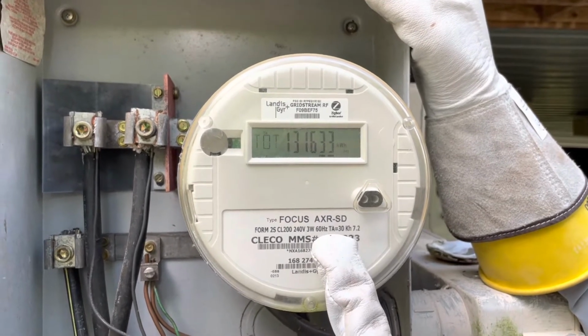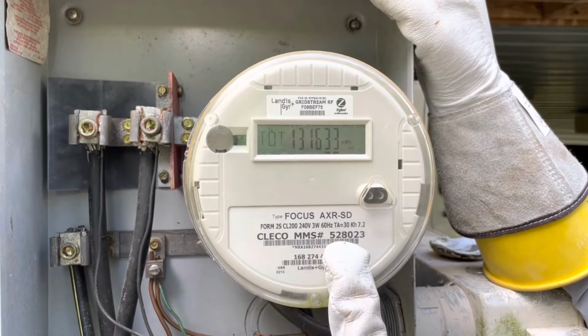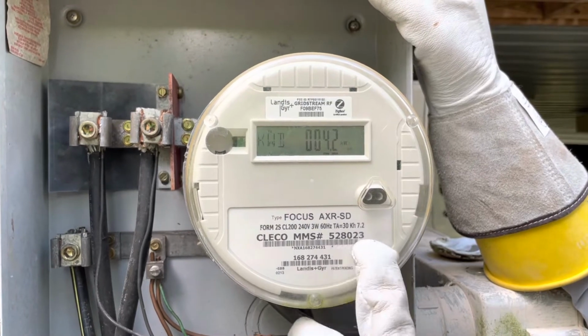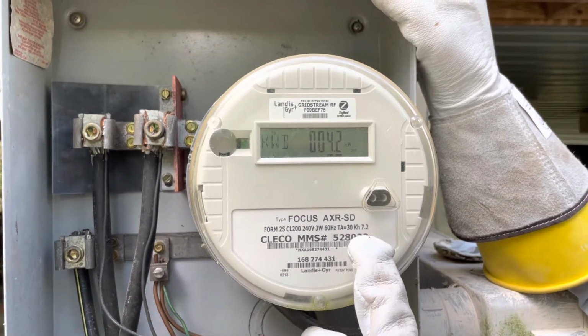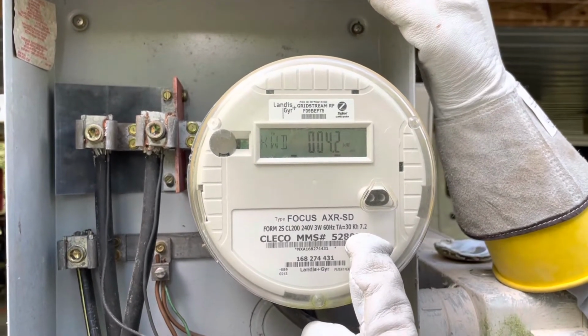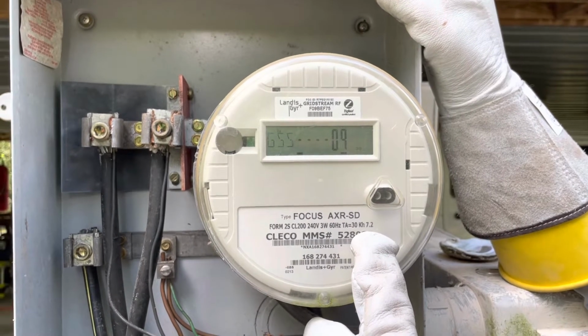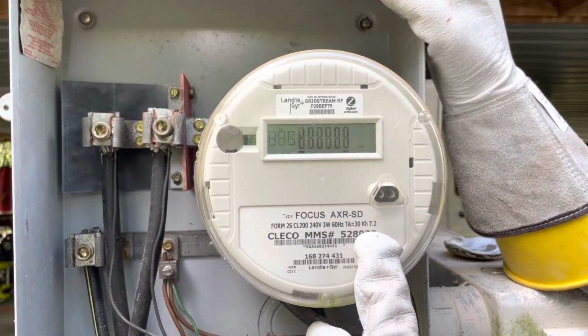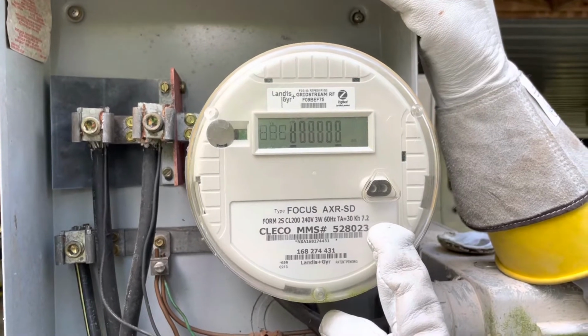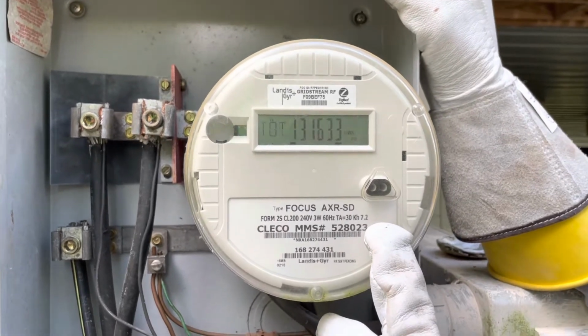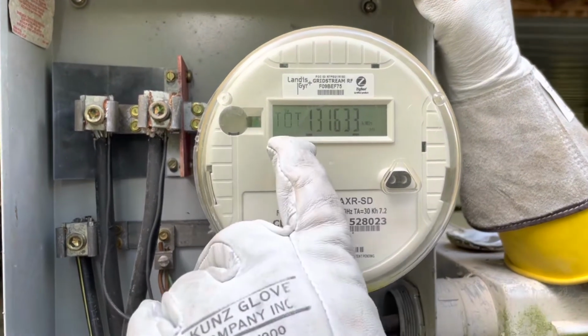It's a 60 hertz system. Cleco runs on 60 hertz. So do all American companies. The test amps is 30, and that's just what you test it at when you're testing the meter for calibration accuracy. And the Kh of 7.2 is for every 1 revolution.